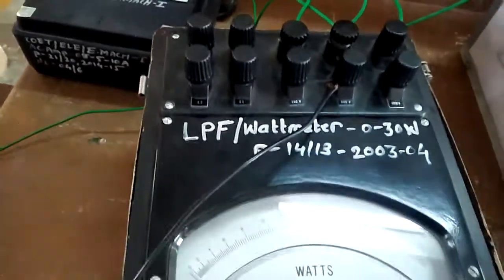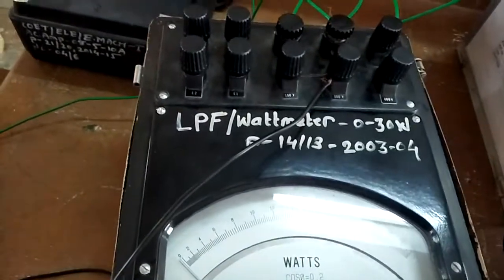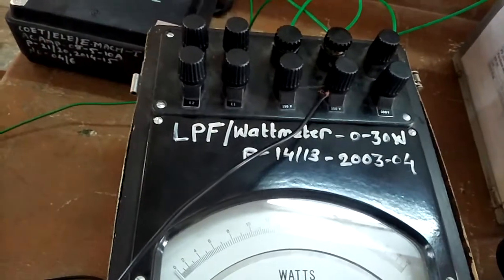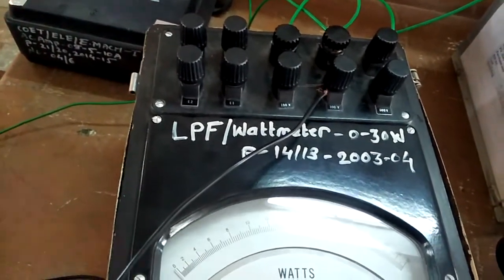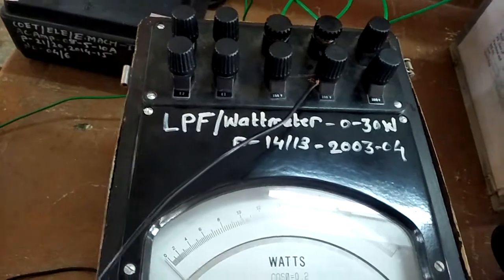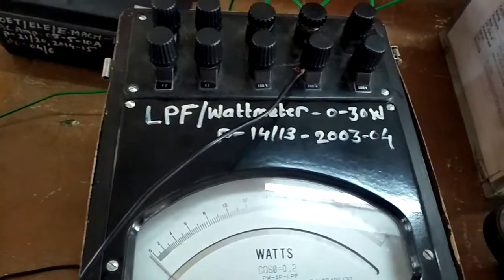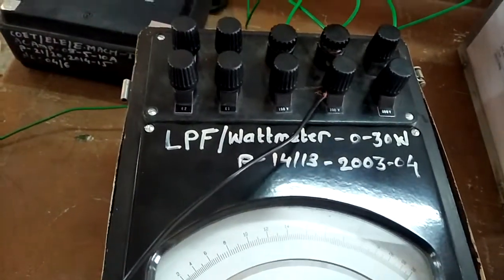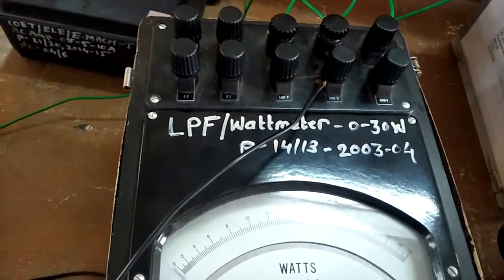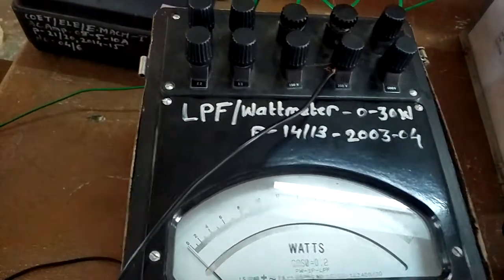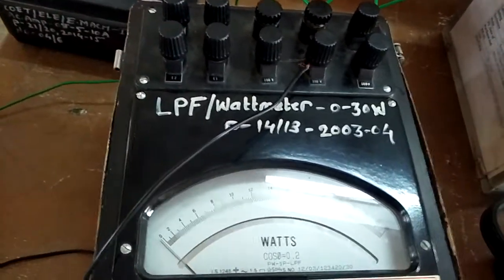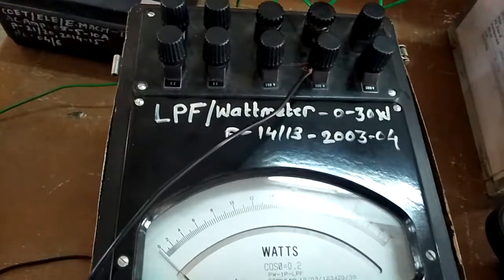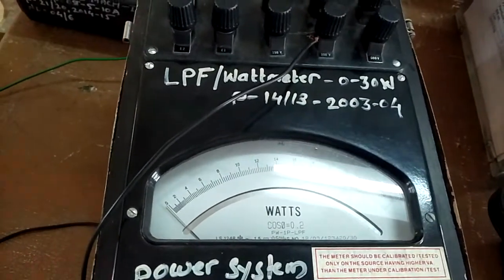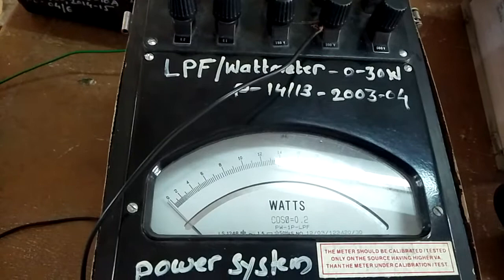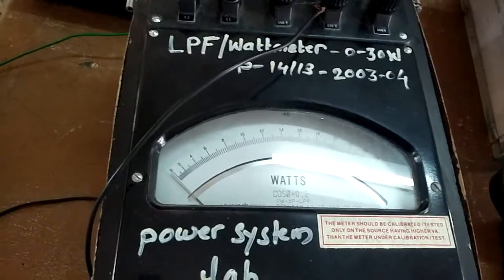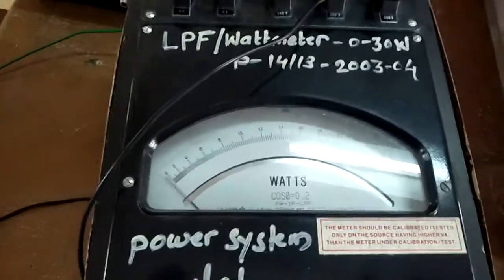Under no load condition, the transformer power factor is very poor. It is 0.2, 0.1, or it may be 0.3 and like that. So if you measure the power with a regular wattmeter, it does not show the proper reading. So it is necessary to measure the power under no load condition as well as in the short circuit condition with a wattmeter which is LPF. It is a low power factor meter, isn't it?